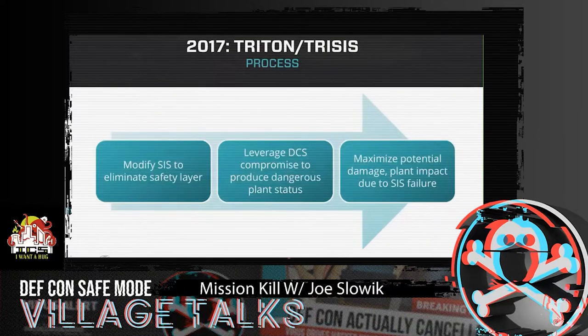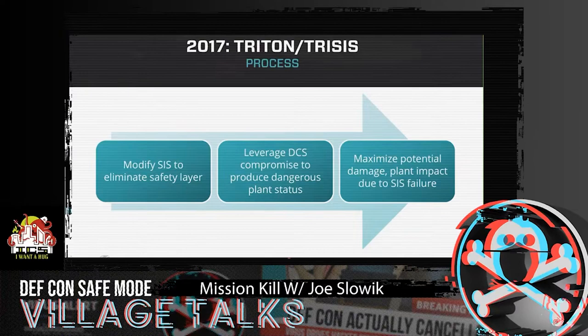What's interesting is that Triton/Trisis, kind of like the 2016 event, didn't work as the attackers intended. It looks like the intended attack was to modify the SIS to eliminate the safety layer, then leverage compromise of the DCS to produce a dangerous state that would propagate beyond the safety layer to cause physical process disruption. Instead, at the time of installation of the Trisis malware — which happened at least twice within the environment — an error within how the malware was put together caused the safety system to trip, the plant shut down. This is still very disruptive and costly, but doesn't result in the damage that would have happened had this attack actually worked as designed. Attackers are getting smarter but still have a ways to go before doing so successfully on a consistent basis.